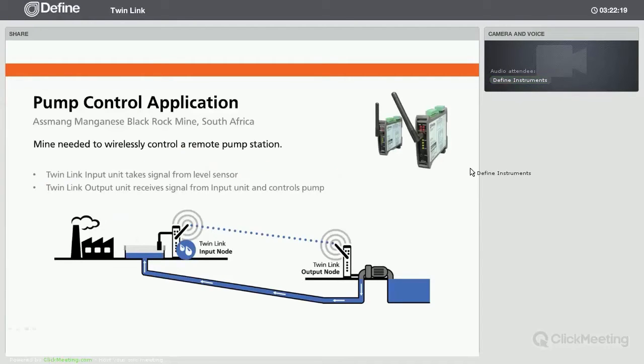Here I'm showing you a very similar application to the one I've just shown you. In this application, the input unit is measuring a 4 to 20 milliamp signal from a level sensor in a tank. When the tank reaches a full level, we want the pump to switch off, and when the tank reaches a low level, we want to turn the pump on. This is being done simply and quickly by configuring the set point functions on the input unit.